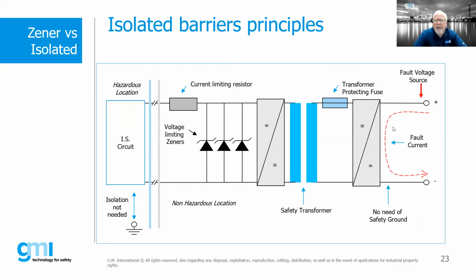Now an isolated barrier, if you see it, looks very similar. We again have a current limiting resistor and a fuse, in this case protecting the safety transformer. Notice we have our safety transformer in the middle here. So we're basically taking the signal coming from this point and transferring it over, mimicking or sending that signal back out to the hazardous location.